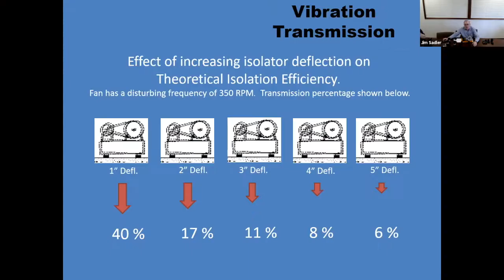So the efficiency idea, and a rule of thumb, is that if the driving frequency, the operating speed of the equipment, is 3 times as great as the natural frequency of the supports, you're going to eliminate 90% of the vibration from reaching the structure. So way back before I started, that was a common specification that all isolation was to be 90% efficient.